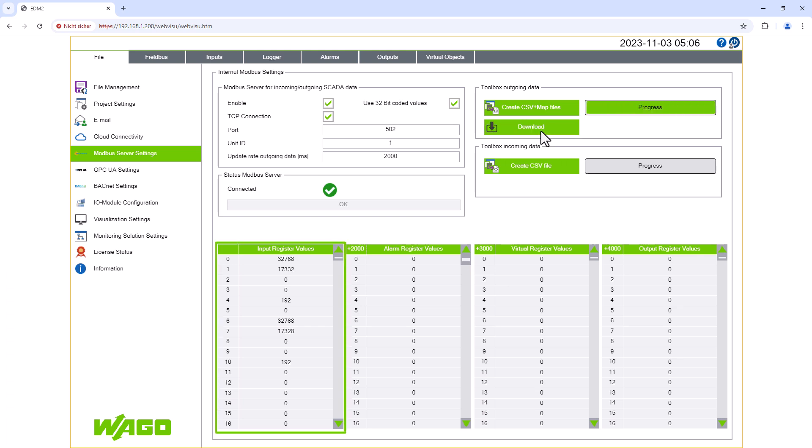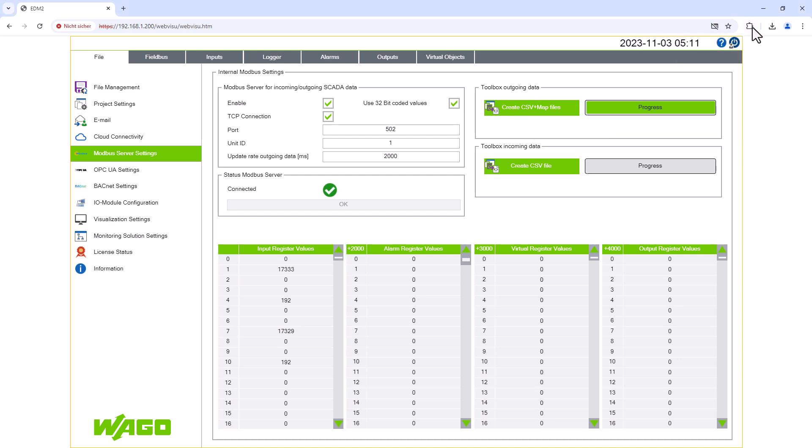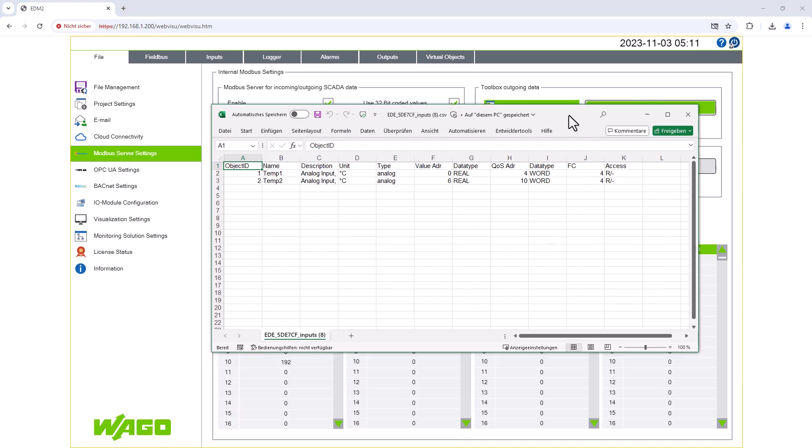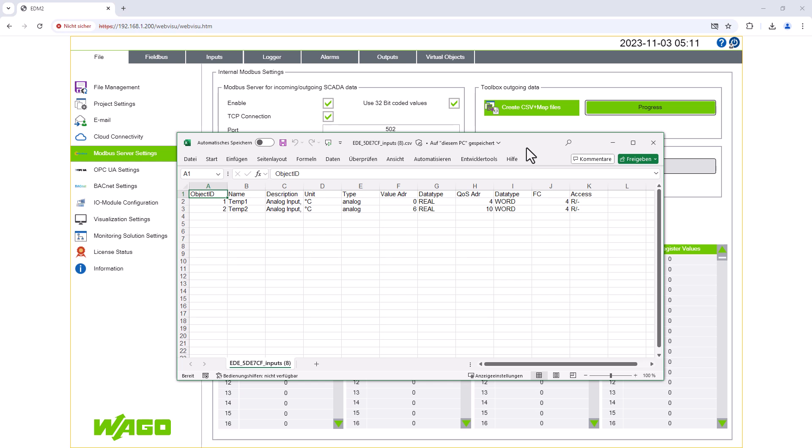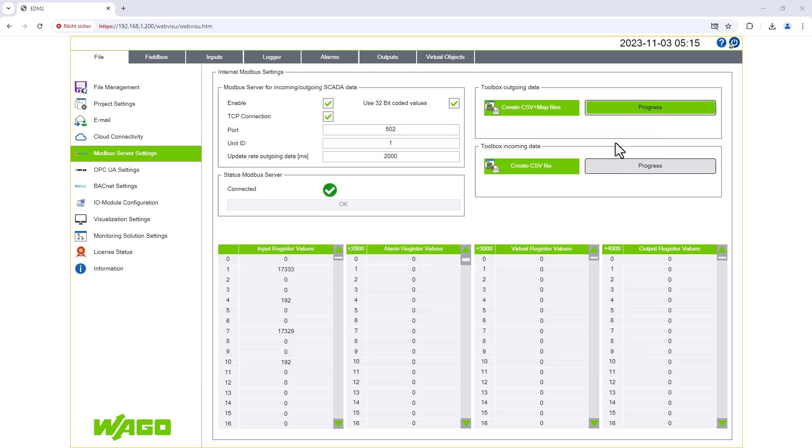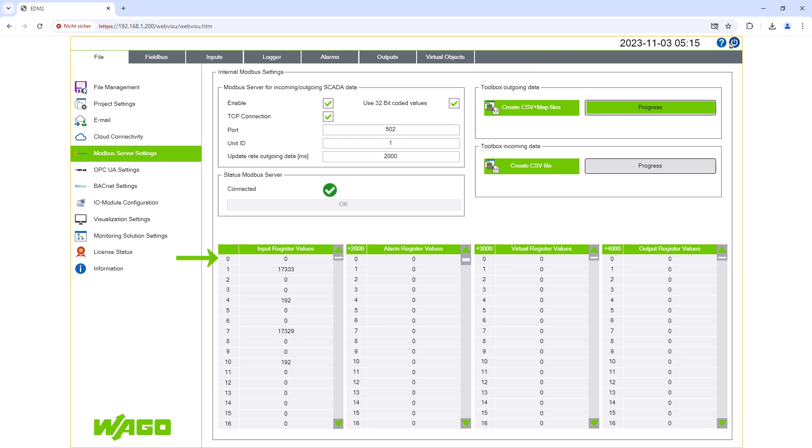The Modbus registers now contain some cryptic numbers. We can then find the two analog values in the generated CSV file. The Modbus register address of the value is then given in the Value Address column. Each measured value is transmitted with a total of six words, even if we choose 64-bit encoding. The first two words contain the actual measurement.